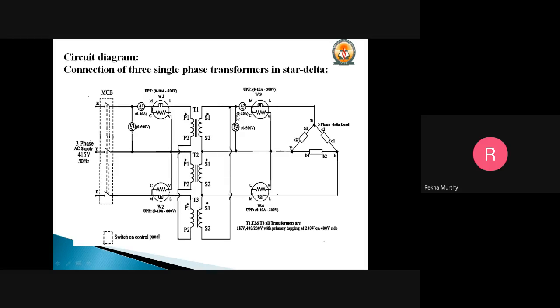The secondary part of the circuit should be in delta fashion. Delta means S1 should be connected to one end of the supply, and S2 also connected to the other end. We must ensure the starting end is connected to the load side. The finishing end, S2, should be connected to the starting end of the second transformer, S1. So S2 and S1 should be shorted.